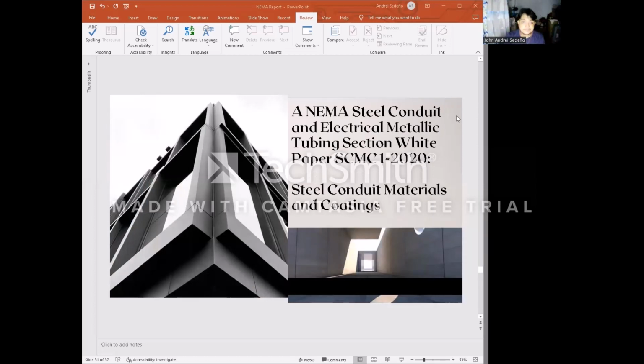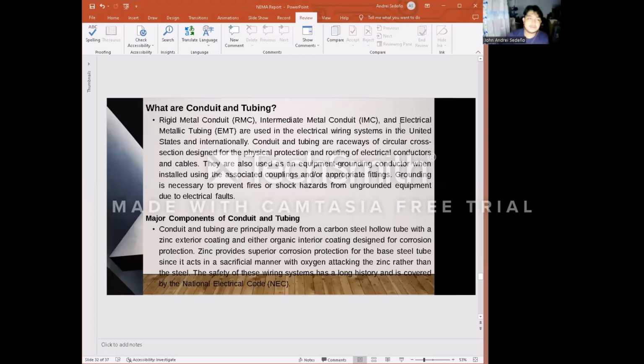So next is the NEMA steel conduit and electrical metallic tubing white paper. Steel conduit materials and coating. So what are the conduit and tubing? Rigid metal conduit or RMC, intermediate metal conduit or IMC, and electrical metallic tubing or EMT are used in electrical wiring systems in the United States and internationally.